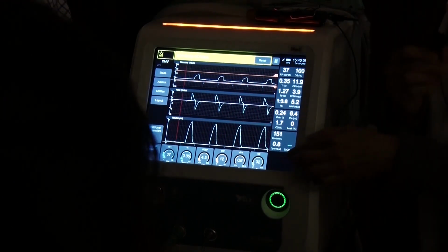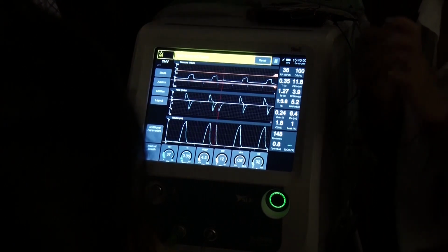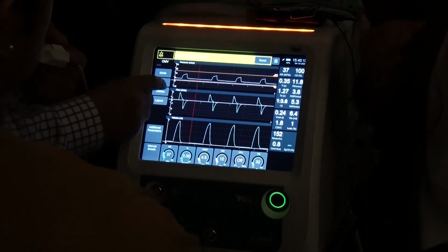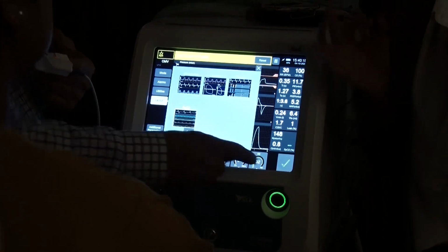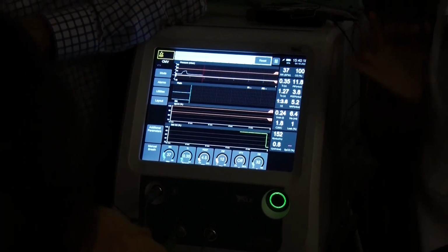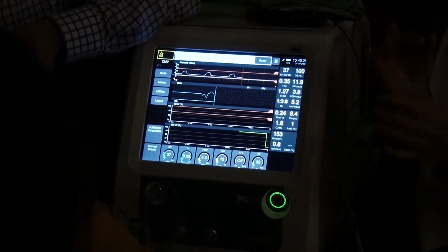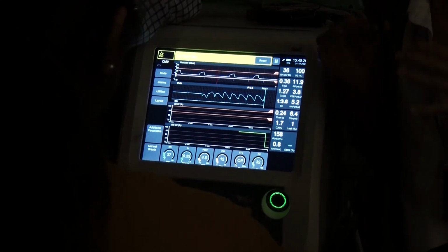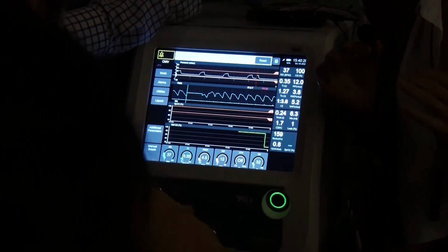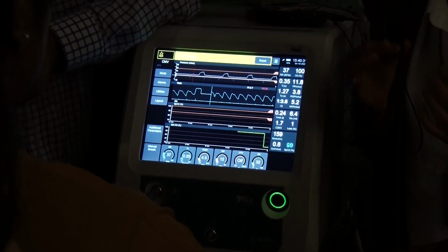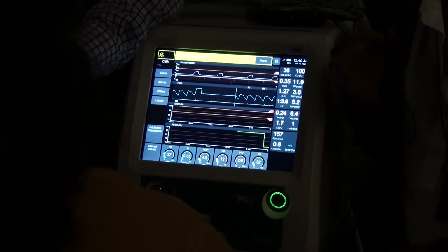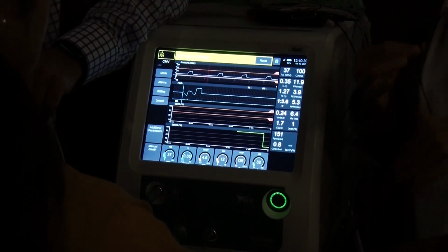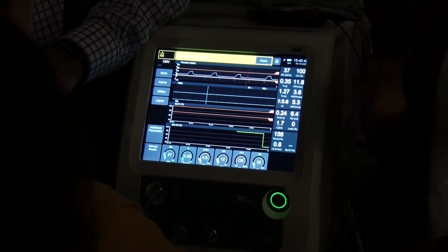Before starting Oxygenie, one very important point: the ventilator will take into account how sick your lung is, with a shunt and things like that, and it looks at 1 hour of data. When you start, of course, you don't have 1 hour of data, so the ventilator will use the FiO2 that you set as a starting point to assess how sick your lung is. If you start at 21%, but the base requirement of your patient is around 30 outside of the episode of hypoxemia or hyperoxia, the ventilator will be running after your patient.